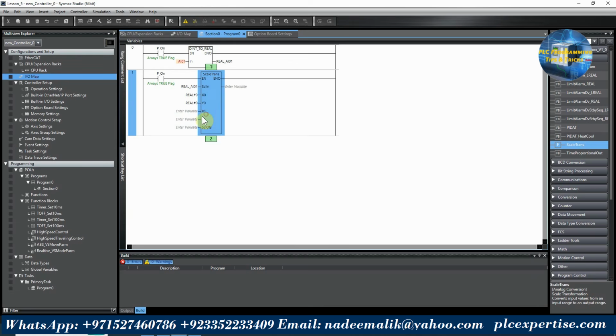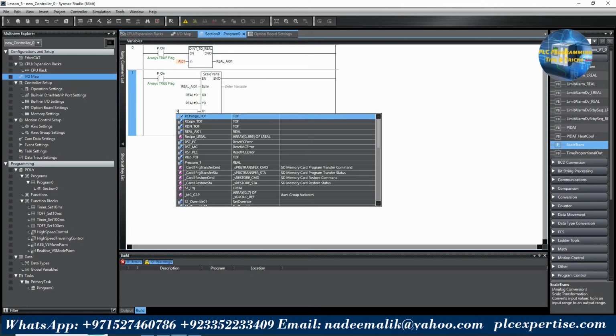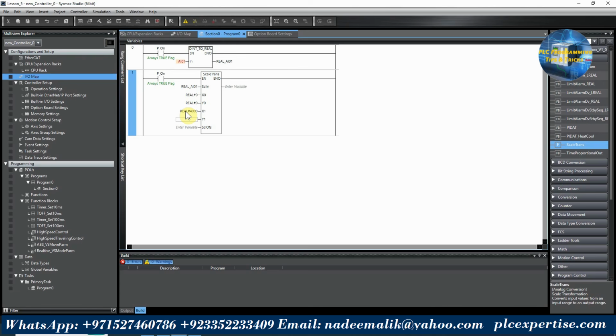This is the X1, which is the raw value max limit. As we have discussed earlier, we are getting 4000 at the 10 volts input. So we will put here real hash 4000. Next is the Y1. Y1 is the maximum engineering value for this transmitter. As we have discussed earlier, our pressure sensor range is 0 to 8.5 bar. So we will put here real hash 8.5.